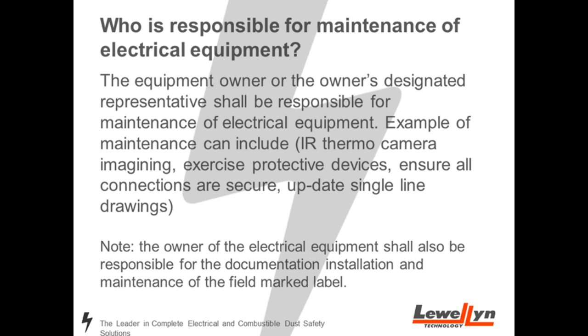Well, they tightened it up a little bit this year. They basically stated that whoever owns the equipment needs to be the one that puts the stickers on, does the arc flash assessment, the incident energy calculations. It's the owner's responsibility or their designated representative, but they have to work together. If you're struggling with this, I'd be happy to have further discussions after the call today to help you get that done. But there's been more emphasis on making sure whoever owns the equipment is responsible for it. That was a change in the 2015 edition.